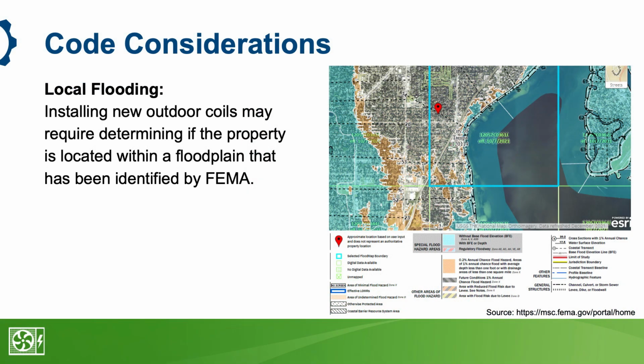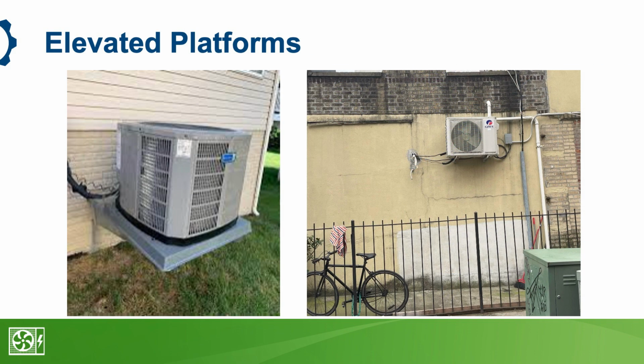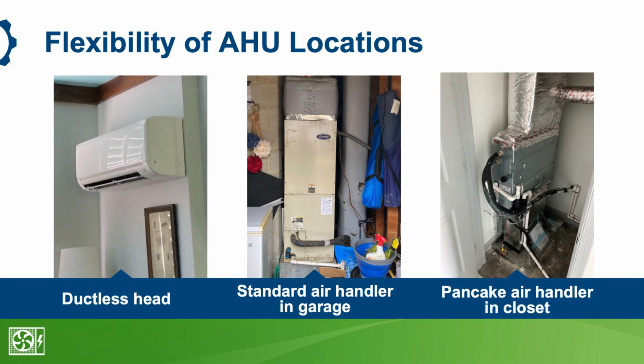When installing split systems, where there's the air handler inside and the compressor outside the building, you should consult local FEMA maps to make sure that the outdoor unit is safe from flooding. Many homes and buildings mount outside units on platforms well above grade, and this can be in response to flooding or maybe it's security. And sometimes they have to be elevated because of steep slopes next to the building. When thinking about where to locate the inside unit, heat pumps offer much greater flexibility compared to fossil fuel equipment.